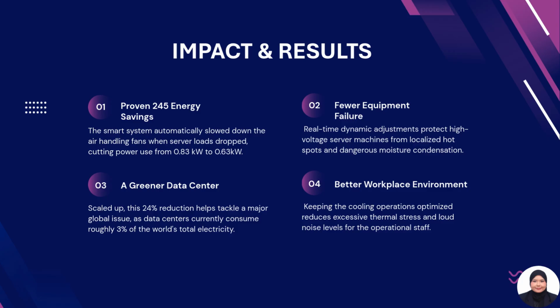For the impact and results, the first is proven 24% energy saving, where the smart system automatically slows down the air handling fans when server loads drop, cutting power from 0.83 kilowatts to 0.63 kilowatts.